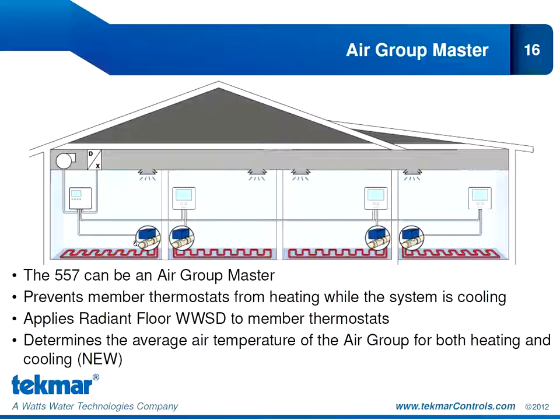The idea behind an air group master is to integrate the heating and cooling operations for zones that share the same ductwork. And we do that so we can avoid simultaneous heating and cooling. The 557 will average the temperatures from all the members of the air group to determine when to enable the equipment. When we're in cooling mode, the 557 will prevent all these thermostats from operating the radiant floor, so we don't have simultaneous heating and cooling.